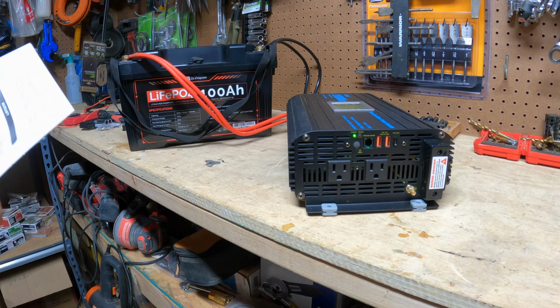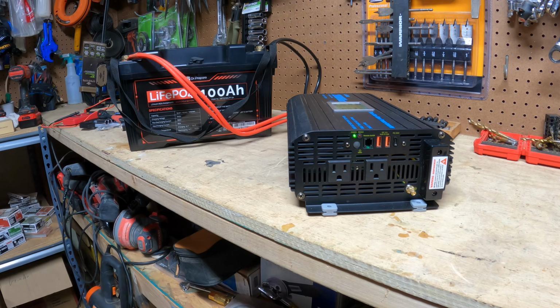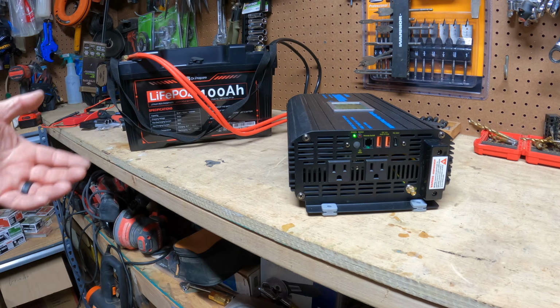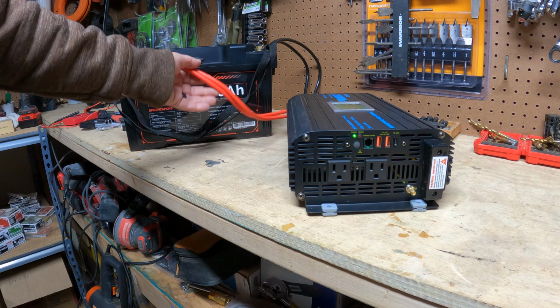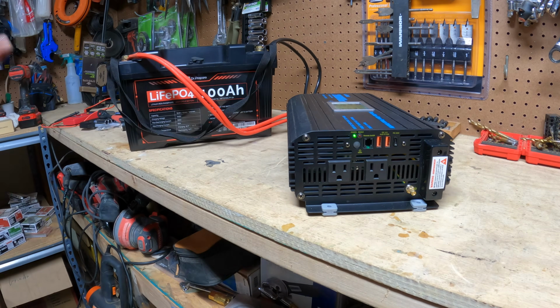So I'm not exactly sure what that is. The closest thing it says about that in the manual is if you've fully discharged it at a continuous 100 amp, they do not recommend recharging it at 50 amps immediately, which will trigger high temperature charging protection. So maybe the BMS is hitting high temperature protection because of the load and it shuts the battery down.